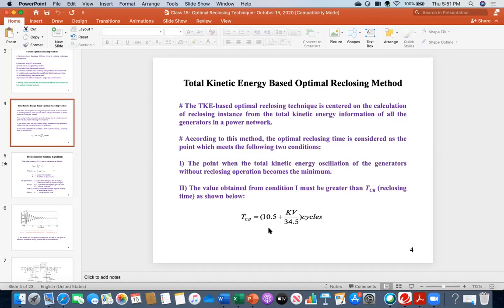Now what is that? It is TCB, the reclosing time. This is called an empirical equation. Power engineers, especially experts on circuit breakers, explored this equation after a lot of trial and error. That at least TCB should be this value. Therefore, if the value obtained is greater than TCB, only then is it safe to reclose the breaker. If not, then don't reclose.